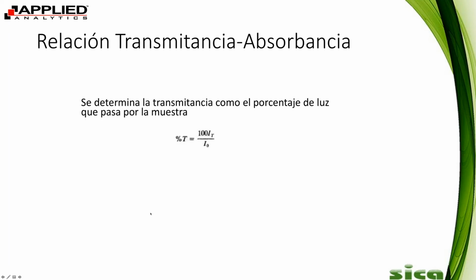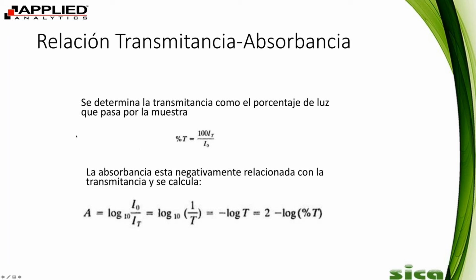Moving on, absorption basically represents how much light was absorbed after it goes through the sample, and percent transmittance is basically the amount of light that successfully passes through the sample. So say you just send a light through the air and it doesn't interact with any chemicals, it's going to be 100% transmission. So this is a physical parameter. It's kind of measuring like a purity. A common application here would be measuring MEG transmittance, or something like that. And you can see down on the bottom, absorbance and transmittance are also easily correlated.